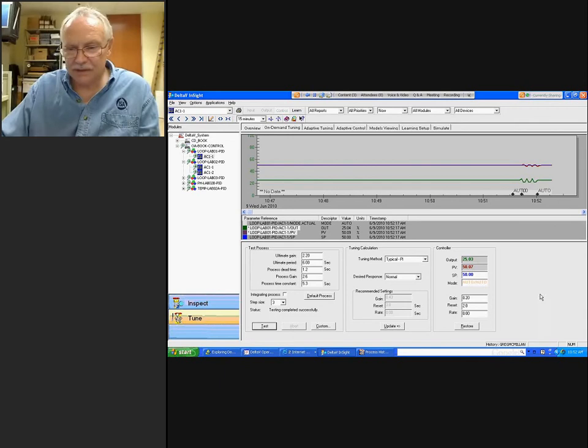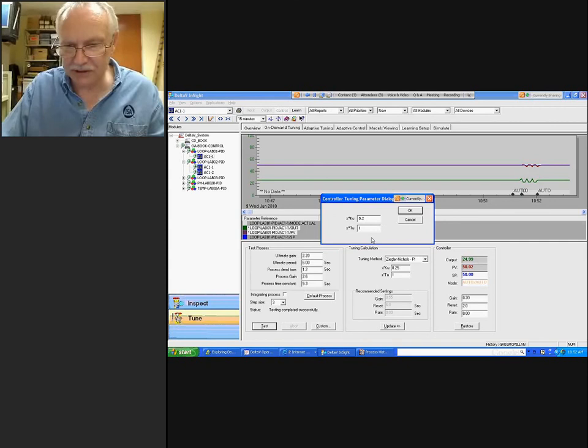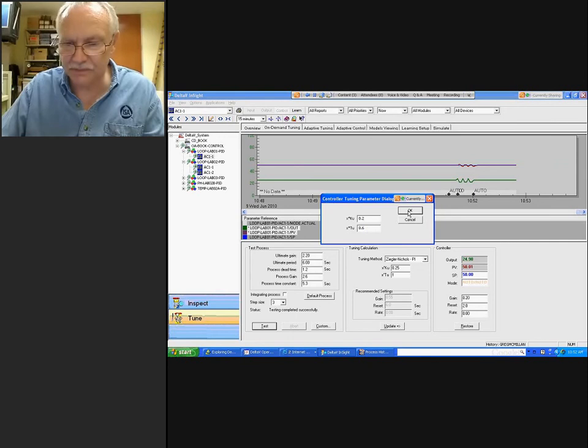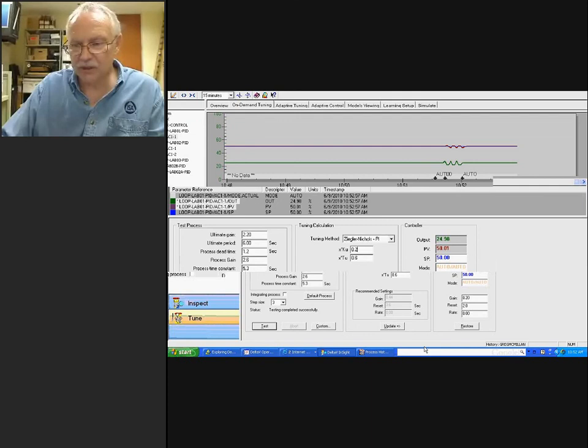And again, I would normally use the Ziegler-Nichols closed loop oscillation method, but going with about half the factor on the ultimate gain that Ziegler-Nichols originally used as their case for maximum disturbance rejection, but didn't have enough robustness. And then I'm going to enter in, recognizing or approaching dead time dominance, a lower factor for the ultimate period. And if we zoom in here, we can see that we come up with a higher controller gain and a higher reset time than what we're working with right now.